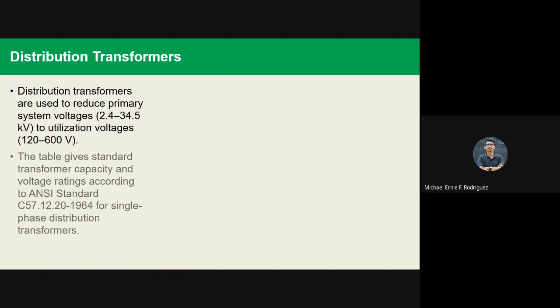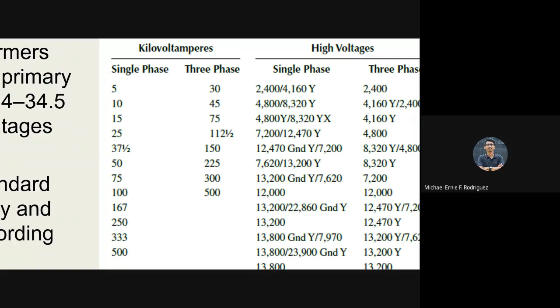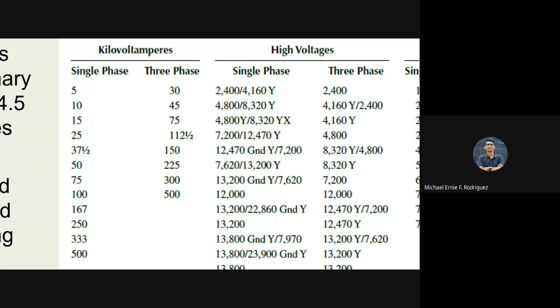So, the table na nakita ninyo gives the standard transformer capacity and voltage ratings according to the ANSI standard 57.12.20-1964 for single-phase distribution transformers. So, meron tayo dito sa table, kilovolt amperes, and then yung high voltages and the low voltages. So, kilovolt amperes na single phase: 5, 10, 15, 25, 37.5, 50, 75, 100, 167, 250, 333, tsaka 500. Okay? Memorize nyo na yan. Three-phase naman na transformer, we have 30 kVA, 45 kVA, 75 kVA, 112.5, 150, 225, 300, tsaka 500.